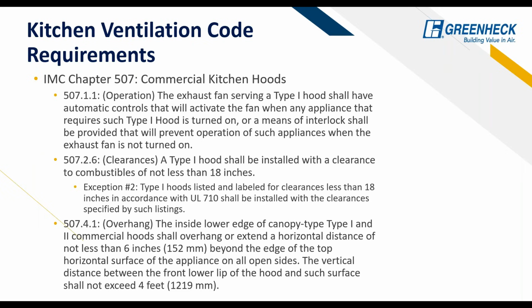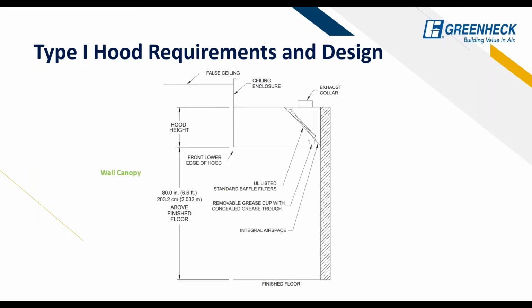Clearances: these hoods need to be installed with a clearance to combustibles of not less than 18 inches. There are some ways around that with zero clearance options that we can provide as well. And then overhang: on all sides of the hood, we require a 6-inch overhang. That does not apply when the hood is up against the back wall. The back wall does not need that, but all other sides need at least a 6-inch overhang for canopy type 1 hoods. If you go to an island hood, it will increase to 12 inches on all sides.